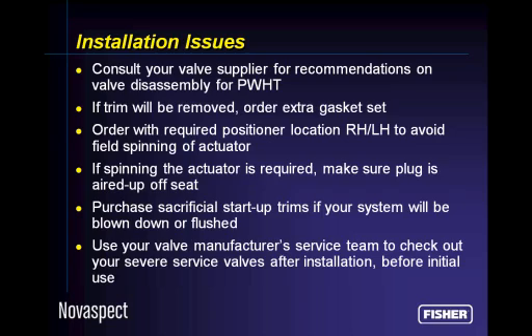And whatever you do, after you install a severe service control valve, please ask the valve manufacturer's service team to come out and run a calibration check and make sure the valve is completely operational before you start it up, because you've spent a lot of money for that valve. Let's make sure that it's ready to run.